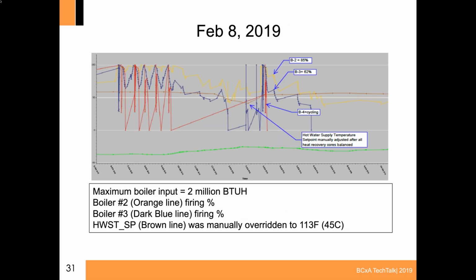Okay, so you can see here that what we're seeing for the boilers is we actually get a percent of the fire of each one of them. And so what we did was we wanted to look at if we could just shut one off, which you can see the boiler 3 goes to off in our trial period. Each one of these boilers is 2 million BTU per hour. So it's quite a significant boiler plant.